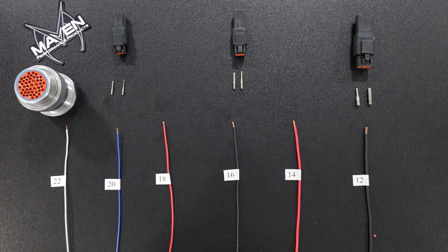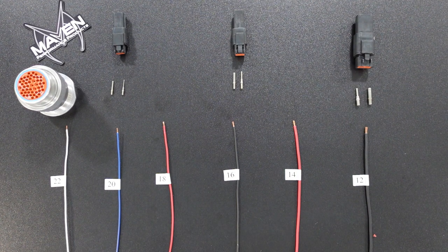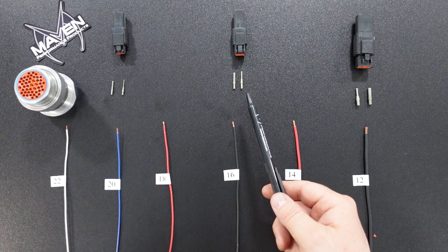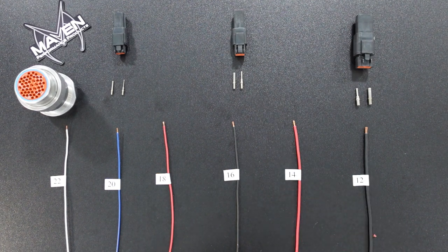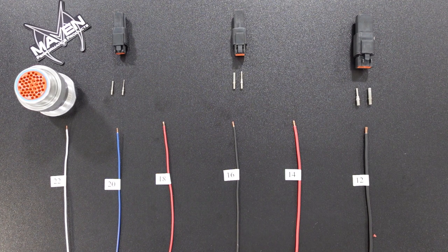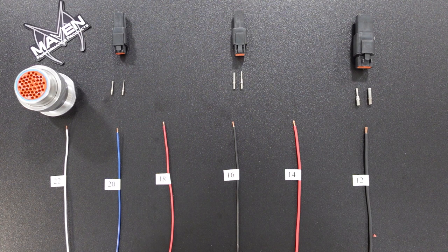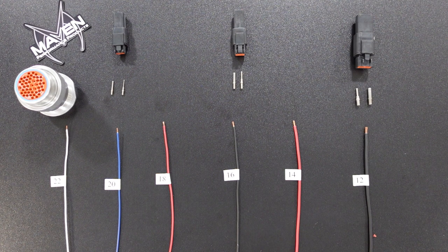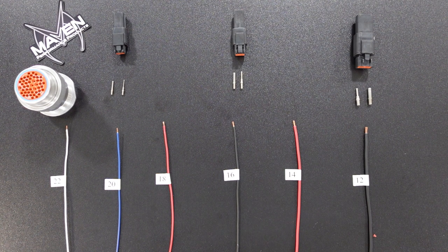The DT series of connectors also uses the same crimp terminals. So the DTM, which is for 20 gauge, the DT, which is for 16 gauge, and the DTP, which is for 12 gauge. When you look at these, you think, well, what happens if I have a 14 gauge or an 18 gauge or a 22 gauge? I can't use these. Well, the short answer is no. We're going to go through what you can do to use these different wire sizes.